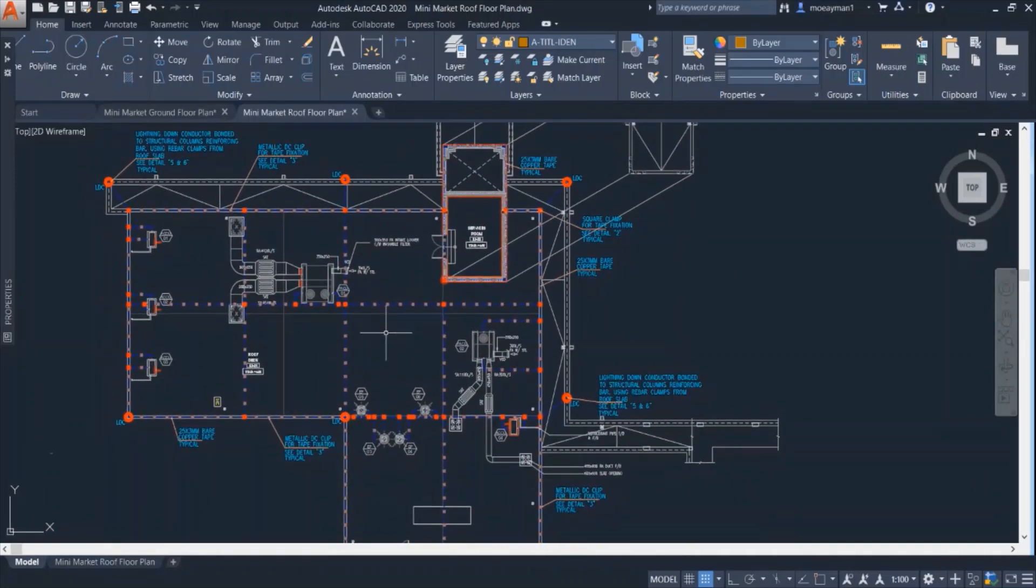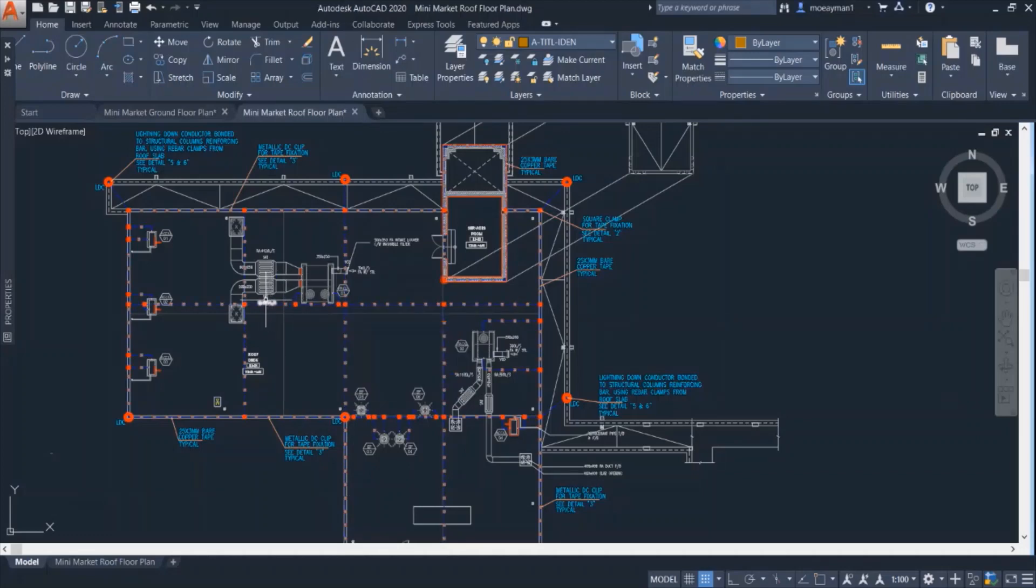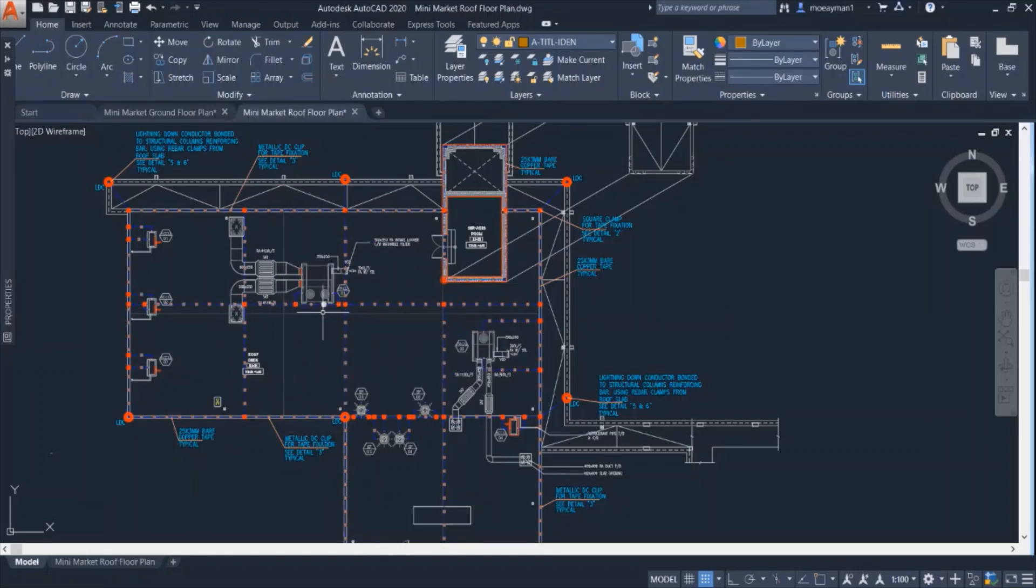At the first glance I think that you shall be able to tell which type of lightning system is implemented in this design. We can see a lot of meshes over here that are intersected together throughout the whole roof. It is actually copper tapes intersected and fixed on the roof of this plan. So based on that we can tell that this is a mesh conductor type.